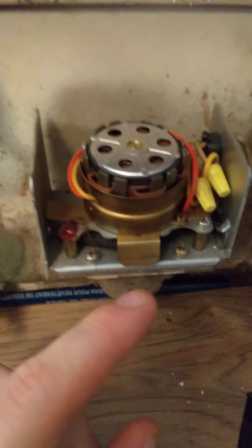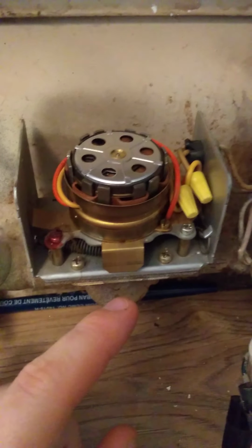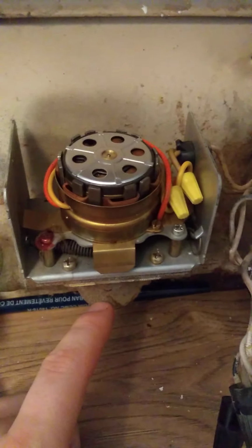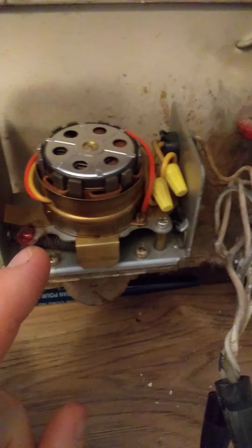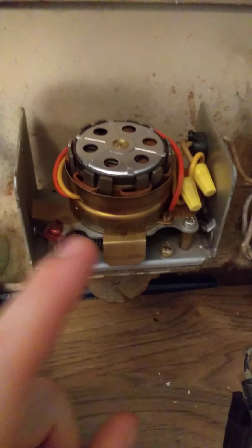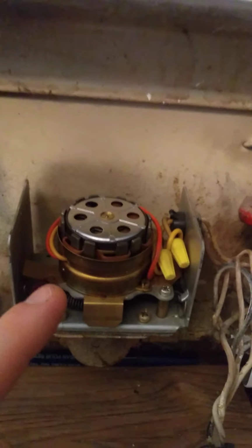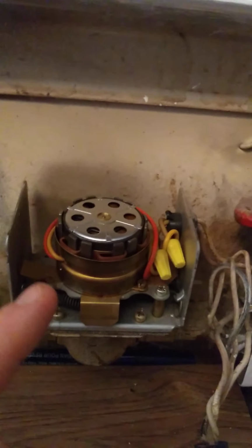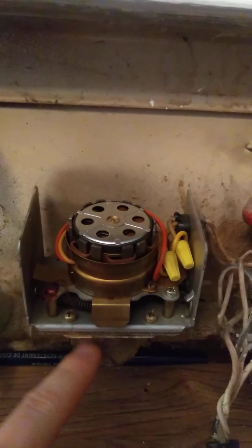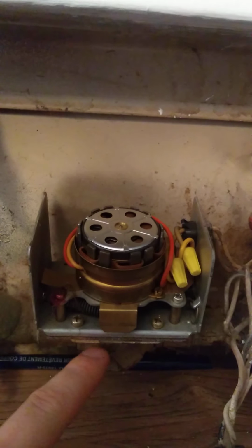So if an owner complains about their zone not working, it's probably this very mechanically and electromechanically complex device that they own that is sitting on top of the very, very simple device that Strata owns. So, like, if I were calling it, I would say there's probably a 98% chance that this complicated stuff fails, probably even a 99% chance that this fails long before this very simple piece that is part of the Strata heating loop system fails.